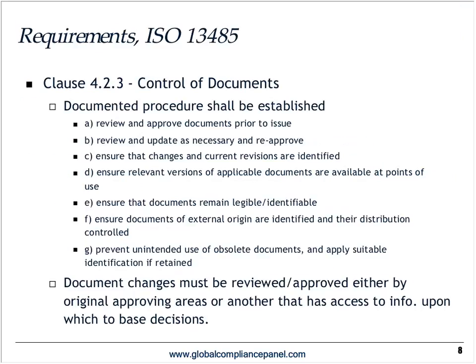When it comes to ISO 13485, the document control requirements in sections A through G closely mirror the FDA requirements: review and approve documents, update as necessary, ensure current revisions are identified, ensure relevant versions are available, documents are legible and identifiable, obsolete documents are prevented from unintended use, and changes are reviewed by original approving areas.